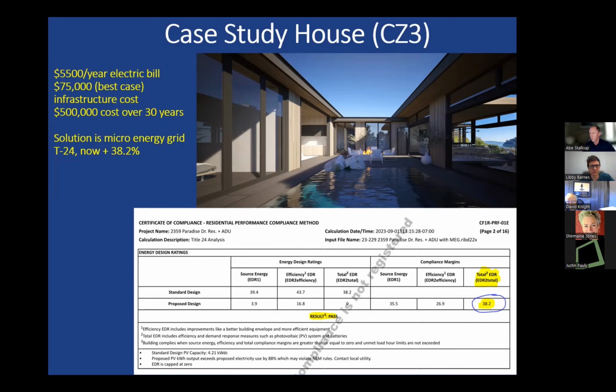You've got electric space heating, electric domestic hot water heating, electric pool heating, electric car charging. It's a house and an ADU. So you've got 2 induction cooktops at 50 amps a pop, 2 electric clothes dryers, and recirc pumps. This is only a 3,500 square foot house, but it still calcs out at 600 amps.